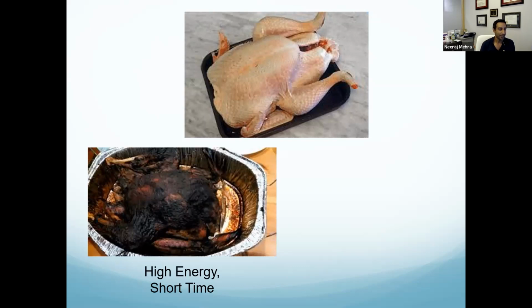And so this is what happens with your coagulation mode. So think about coagulation. Now think about, instead of cooking a turkey, you're trying to stop a bleeding vessel. Well, what's going to happen is you're going to cook that bleeding vessel, and you're going to be like, oh, it's so charred, it's totally cooked. And then you take off your, let's say if you're doing it with a pair of pickups or whatever, and you leave and you're like, oh, it's still bleeding. What's going on here? Well, it's because your char is at high resistance. So you've totally cooked this thing on the outside, but now you've created an area of high resistance, so nothing can get through, and it's completely raw on the inside. So if anyone has ever experienced this, where you take your active electrode and you use coag and you cook that thing and it's char all around and it's still bleeding and you can't figure out why, well, this is why. It's because you cooked it on the outside but not on the inside. So how do we cook a turkey? What's the proper way to cook a turkey?